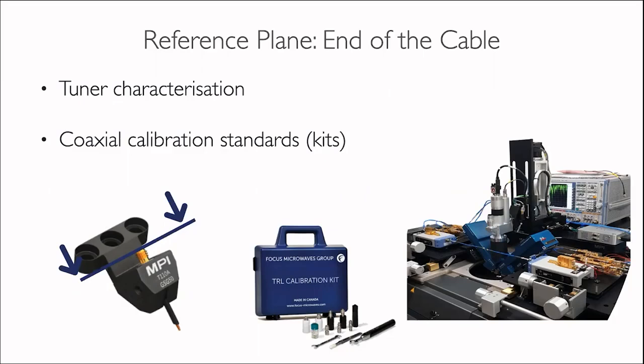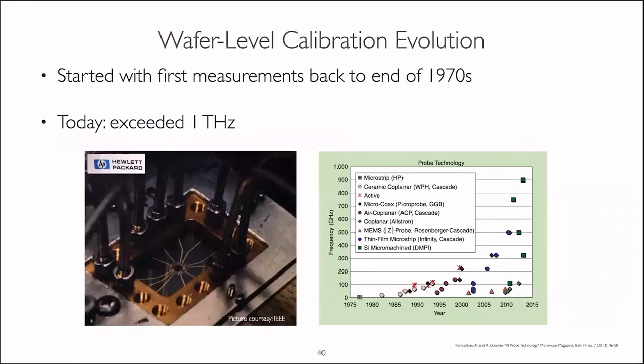When we do cable end calibration, or calibrate our system for coaxial measurements, we use a calibration kit. These are well-defined calibration standards. We know the electrical characteristics defined by the vendor. The standards are easy to operate. We connect them to the end of the cable, and we have very reliable calibration results, in particular when we use the top ranges. When we move to wafer level measurements, actually the situation changes completely. In one of my previous presentations, I mentioned that you basically fall into the rabbit hole like in Alice, and everything flips upside down, and I still have the same feeling when we do the on-wafer cal.